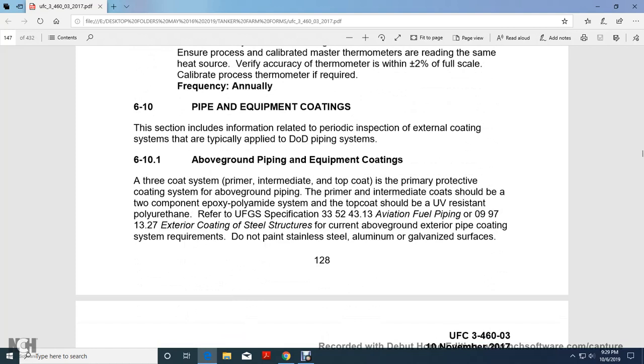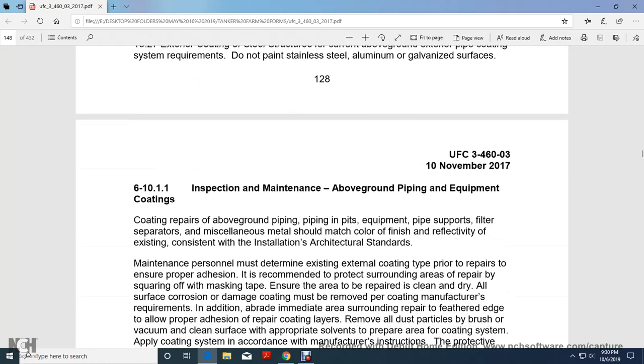Alright, piping and equipment coating system includes the information related to the periodic inspection of the external coating of the system, typically with the Department of Defense piping system. Above ground piping and equipment coatings use a 3 coating system: primer, intermediate, and top coat of the primary protective coating system. For above ground piping, the primer and intermediate coat should be used if the 2-component epoxy polyamide system, and the top coat should be ultraviolet resistant polyurethane. Refer to Unified Guidelines Spec 335243-13, aviation fuel piping, or 09971327, exterior coating steel structures, for the current above ground exterior piping coating system. Do not paint stainless steel, aluminum, or galvanized surfaces.